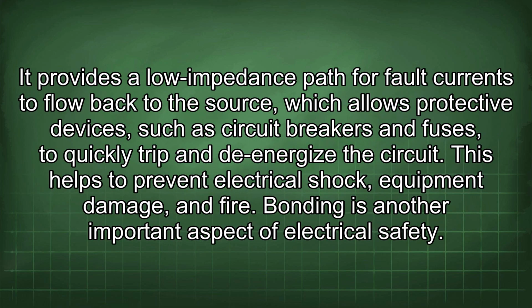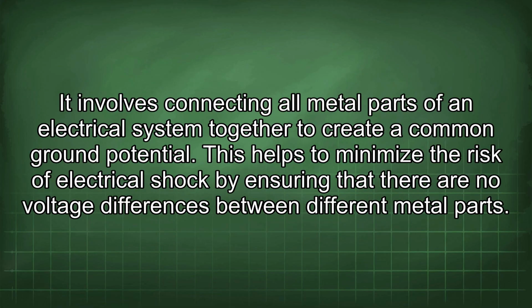It provides a low impedance path for fault currents to flow back to the source, which allows protective devices, such as circuit breakers and fuses, to quickly trip and de-energize the circuit. This helps to prevent electrical shock, equipment damage, and fire. Bonding is another important aspect of electrical safety. It involves connecting all metal parts of an electrical system together to create a common ground potential. This helps to minimize the risk of electrical shock by ensuring that there are no voltage differences between different metal parts.